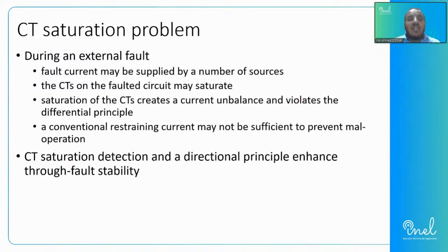So let's zoom in and focus on one of our problems, which we talked about maybe in one of our previous slides, the CT saturation problem. How would the CT saturation problem affect our differential protection? At the end, each CT has a certain core, and it applies a certain electromotive force based on the current. If such a CT is working in the saturation region, the CT would create some unbalanced signal in the current, which violates the operation of differential protection.